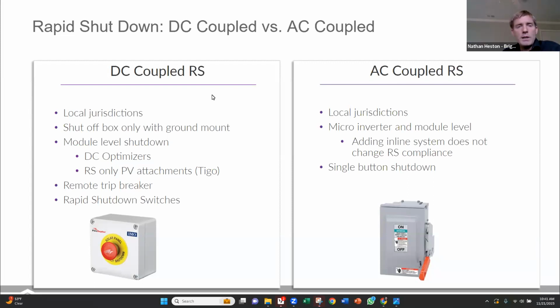What the rapid shutdown device does is it allows the panel to be shut off at the panel level. Essentially, it's a relay, and that relay is receiving a keep alive signal from the inverter. And a rapid shutdown button allows us to shut off the panel at the panel level by turning off that keep alive signal. So the regulations differ from jurisdiction to jurisdiction, but I believe it's a nationwide regulation that all roof mount panels have to have a rapid shutdown device. So you can get module level shutdown through either DC optimizers, so they have that built in, or just rapid shutdown devices like Tigo devices or the AP Smart devices. And our inverter has a built-in AP Smart transmitter which sends that keep alive signal out.